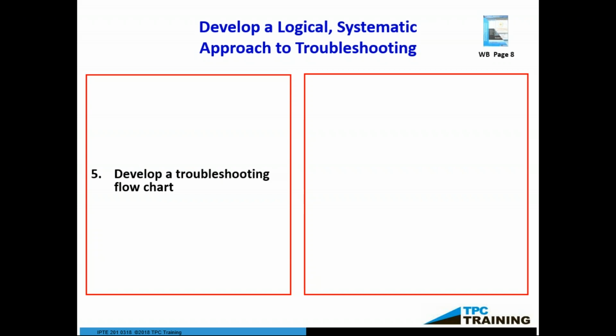If it's yes, then we go to the next step. If it's no, where do I go and check it? You can make these little flow charts, put them on the machine, and have your operator help you with this, because they know what's supposed to happen when, and the timing of the piece of equipment. I don't care if you make a widget, that widget's got to come out every 5 seconds. Well, at second 3 it gets chopped in half, whatever it is, the operator's going to know that. That's how you make up your troubleshooting chart, it's a flow chart.